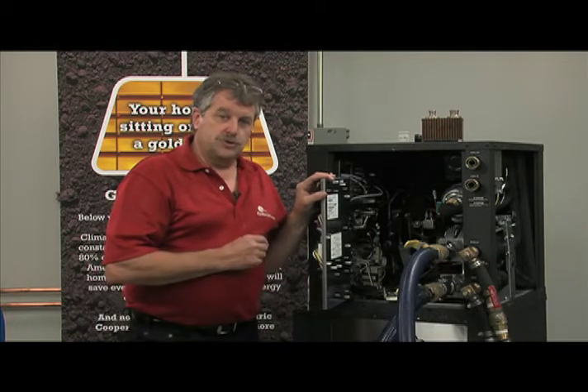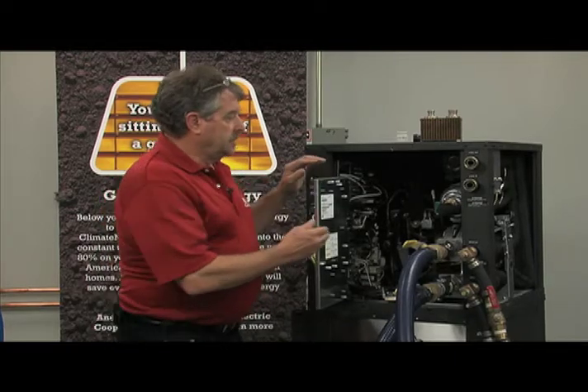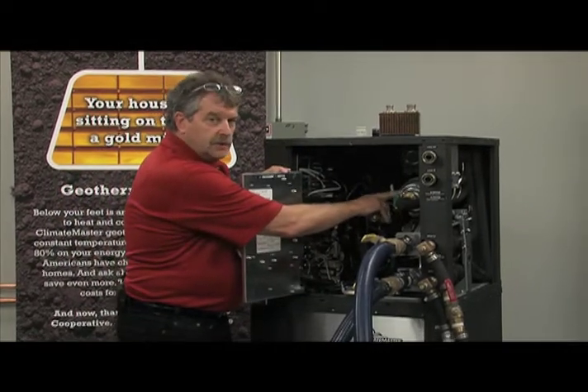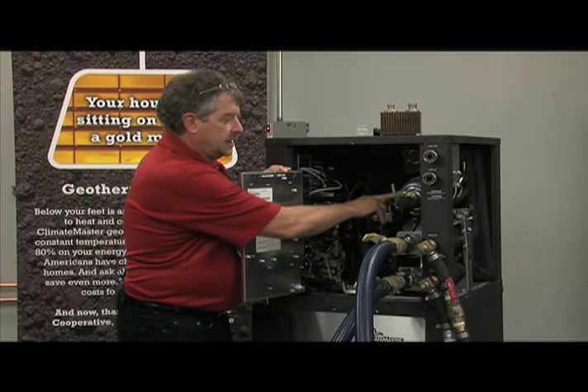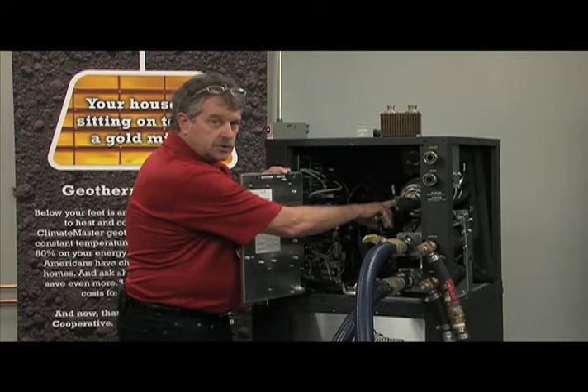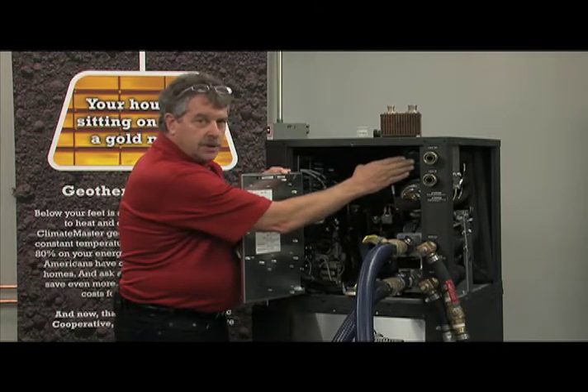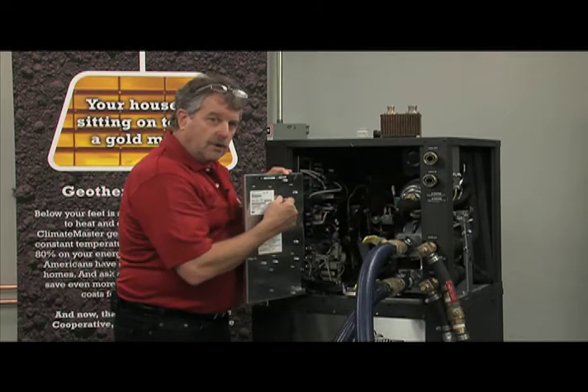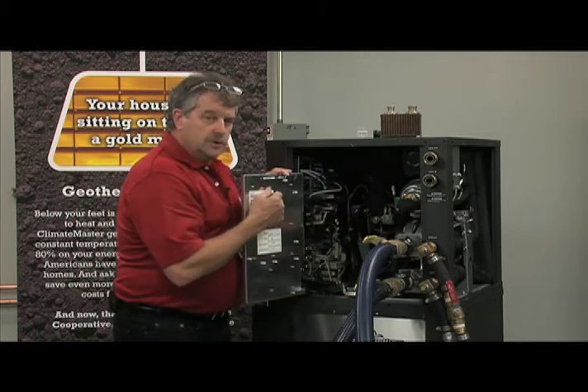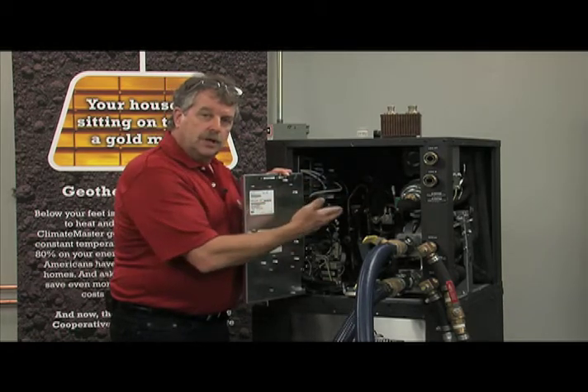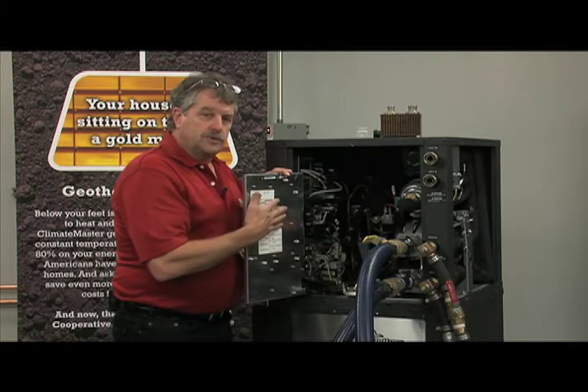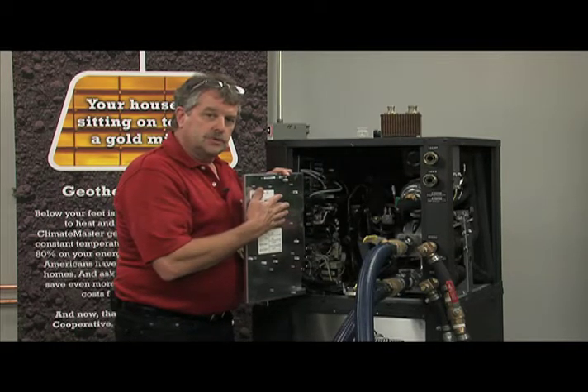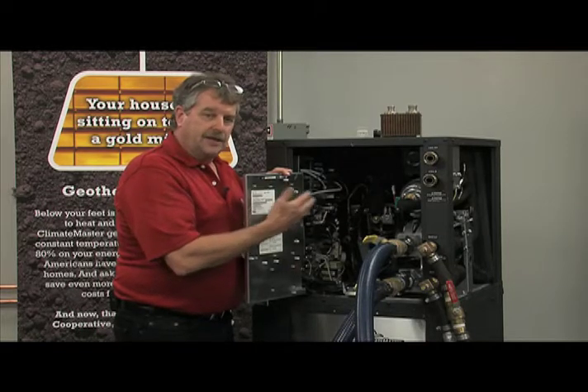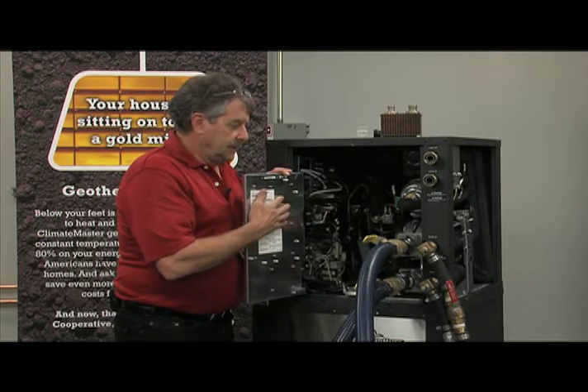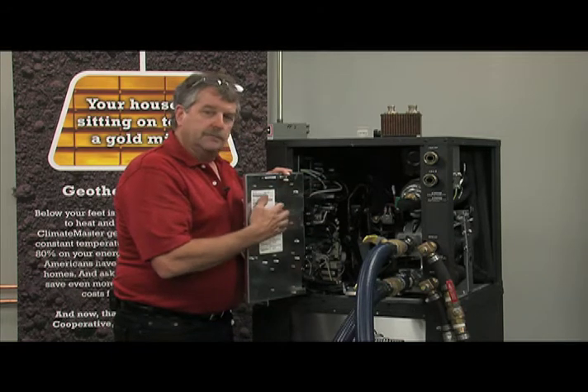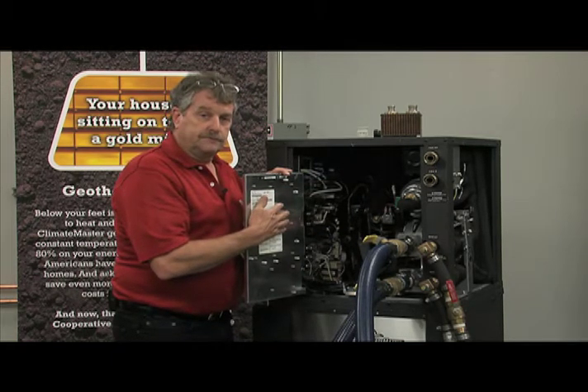So, kind of a pre-flush check for the inside of the unit. You may want to consider validating that you have the valve closed on the expansion tank, as well as making sure that that union is snug. There's also a couple of unions up here on our hot water pump. Again, this is in the Trilogy with hot water product. And then we have a couple of other unions down on the Magna pump, as well as on our Grundfos flow sensor, which we'll reference here in just a short bit. So you may want to consider validating that those are snug, so that you can prevent some cleanup and make less work for yourself.